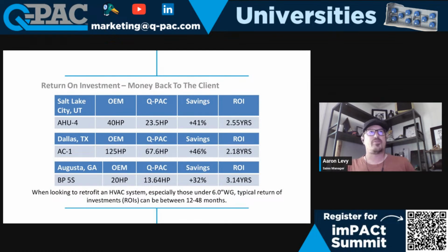These are some other numbers we talked about last month as well, just to reinforce the point. Depending on the application, that 2.5 to 3 year time frame does tend to hold true when you're looking at applications in that 2.5 to 5.5 inches of pressure range. Once we start getting above 7 inches of static, the ROIs do tend to be farther out.